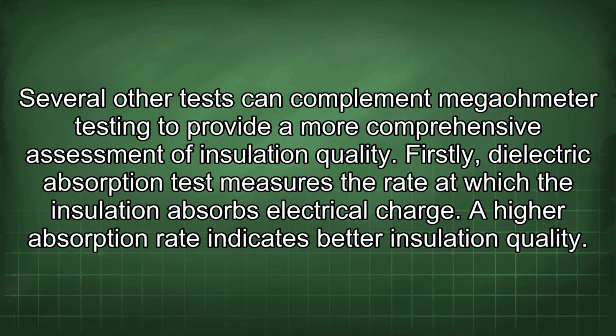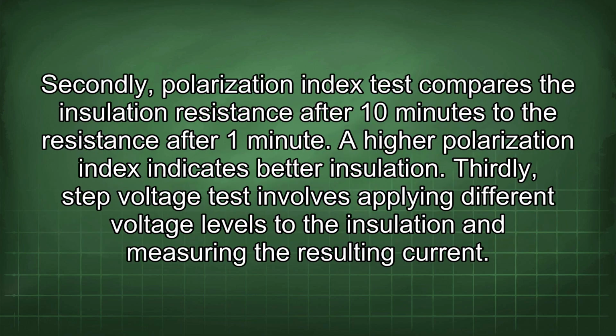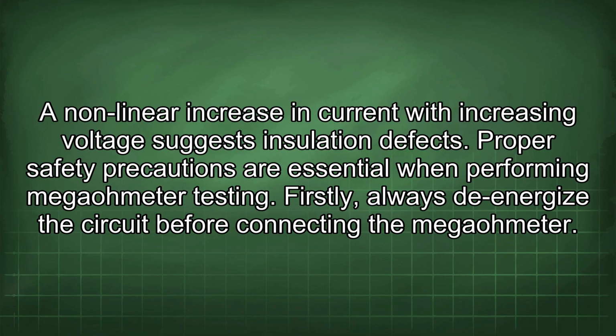Several other tests can complement megaohmeter testing to provide a more comprehensive assessment of insulation quality. Firstly, the dielectric absorption test measures the rate at which the insulation absorbs electrical charge. A higher absorption rate indicates better insulation quality. Secondly, the polarization index test compares the insulation resistance after 10 minutes to the resistance after 1 minute. A higher polarization index indicates better insulation. Thirdly, the step voltage test involves applying different voltage levels to the insulation and measuring the resulting current. A nonlinear increase in current with increasing voltage suggests insulation defects.